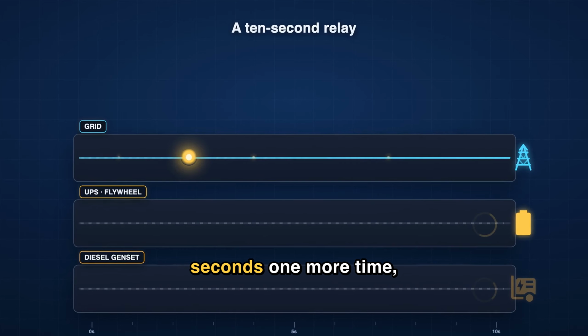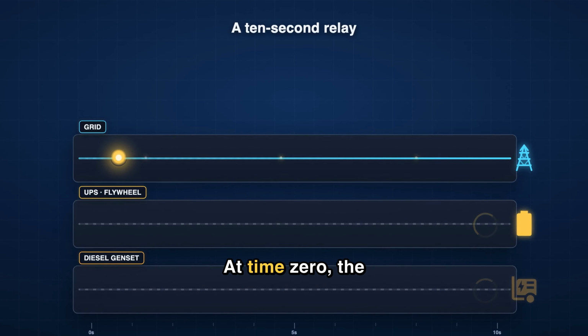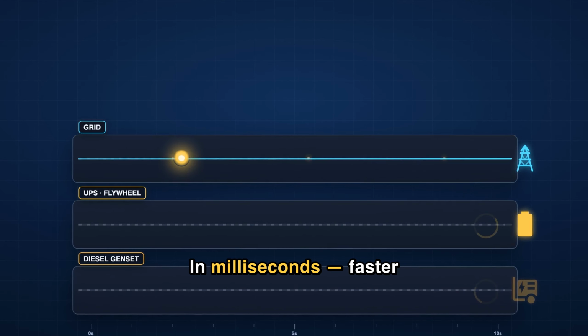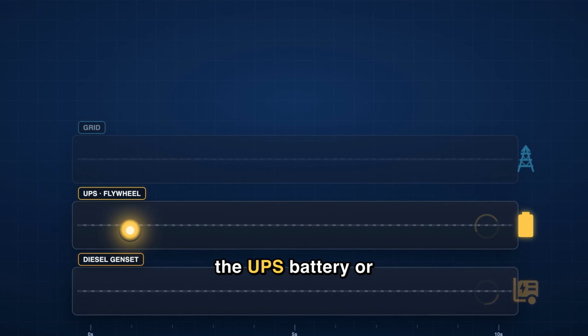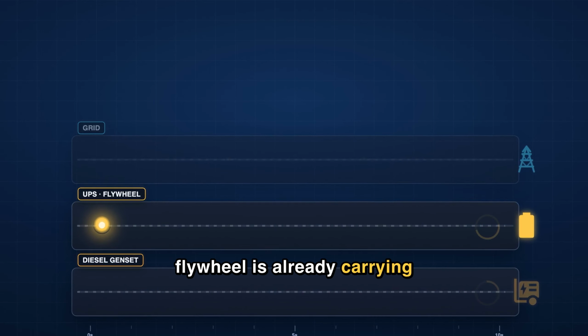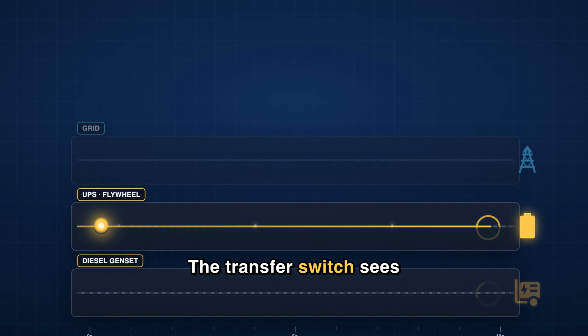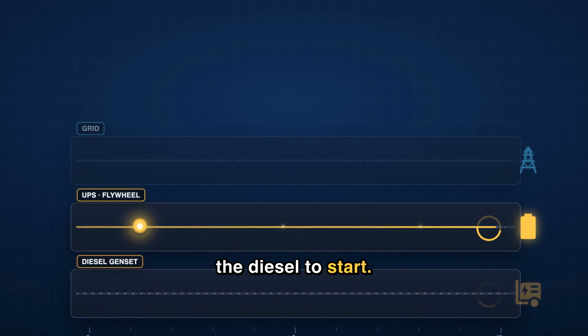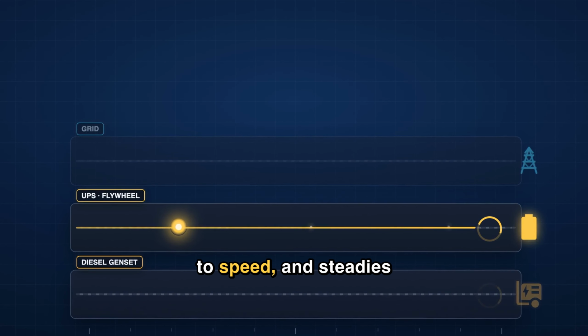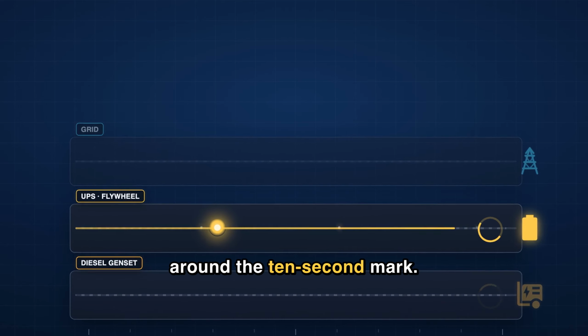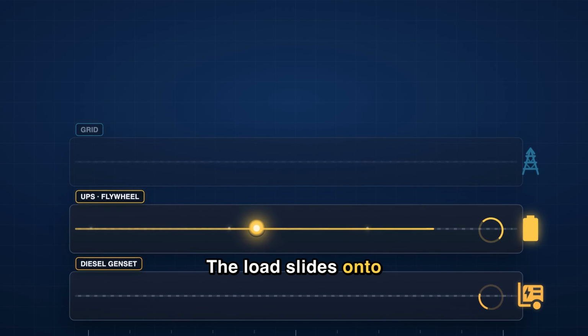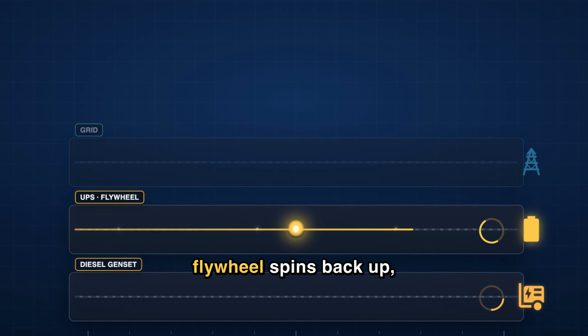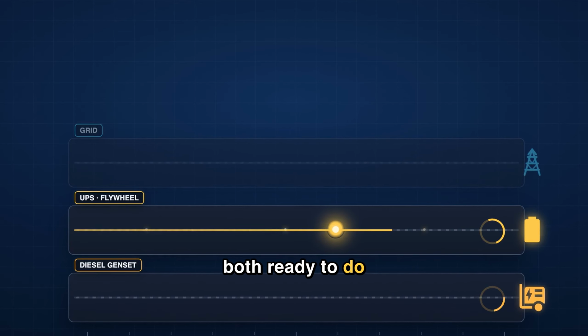Run the whole 10 seconds one more time, end to end. At time 0, the grid dies. In milliseconds, faster than you can blink, the UPS battery or flywheel is already carrying the servers, no flicker. The transfer switch sees the outage and signals the diesel to start. The engine cranks, climbs to speed, and steadies at 60 Hz by around the 10-second mark. The load slides onto the generator. The battery recharges, the flywheel spins back up, both ready to do it all again.